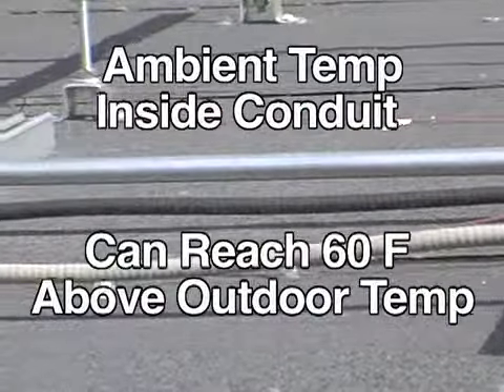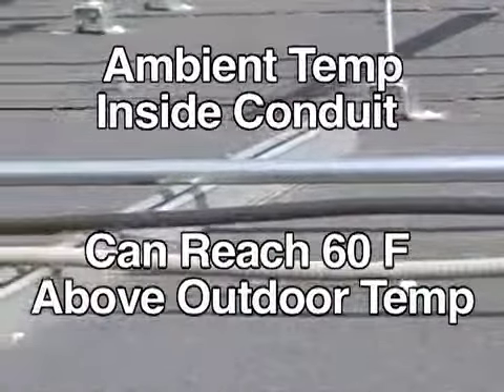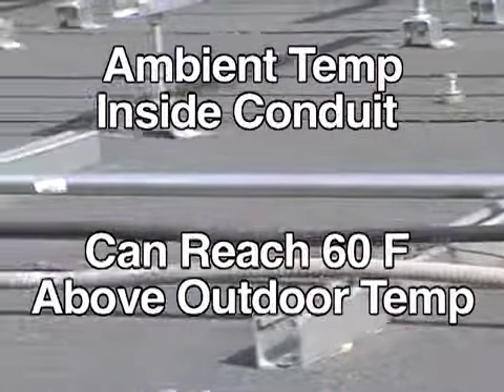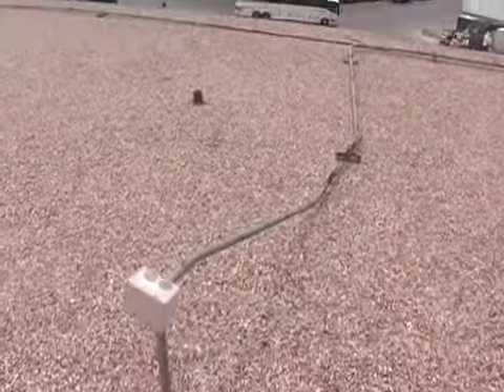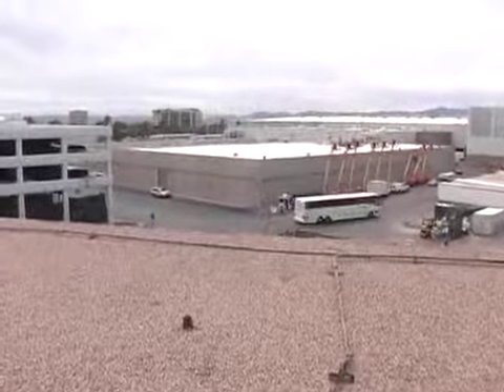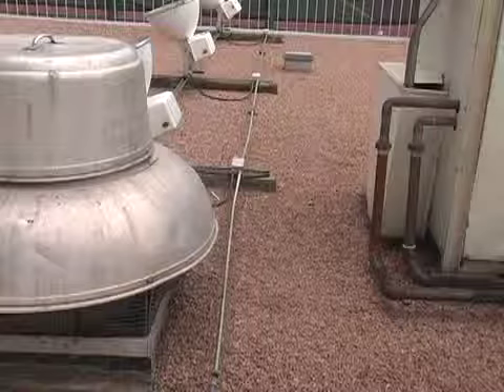What is the temperature inside a conduit located on a rooftop in sunlight? You might be interested to know that it can be more than 60 degrees Fahrenheit higher than the outdoor temperature. We became curious about this temperature differential when inspectors came to us and told us that even in the cooler climates like the Northwest and New England, conduits located in the sunlight got hot.